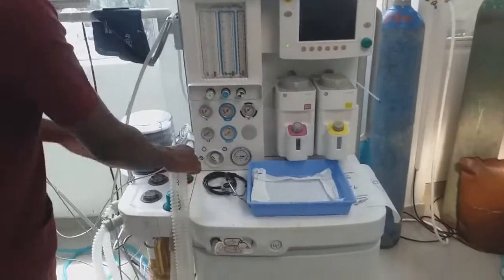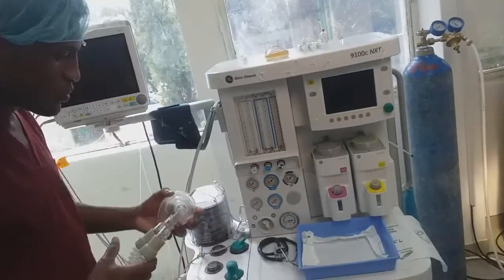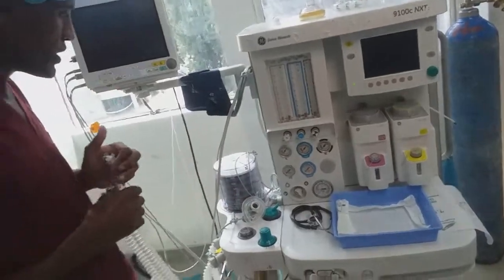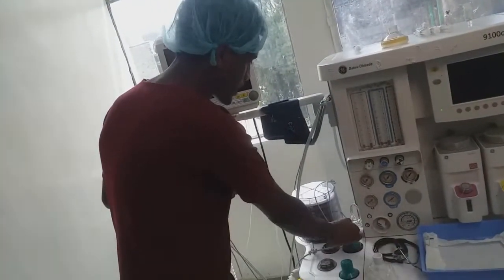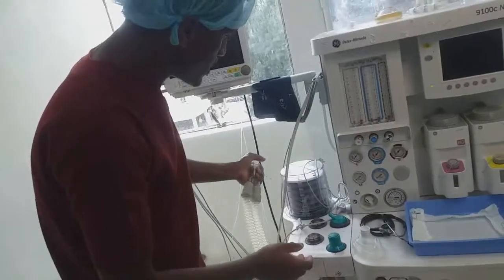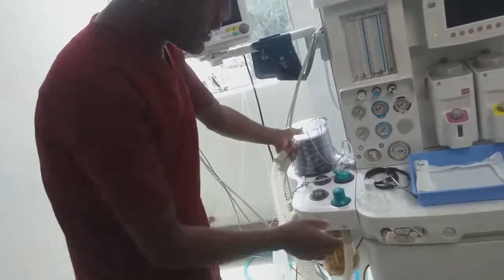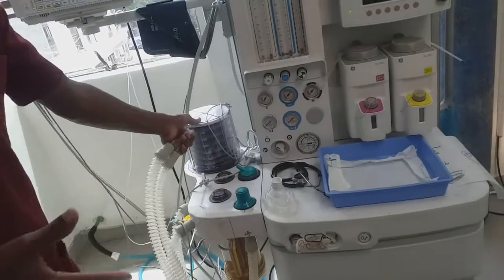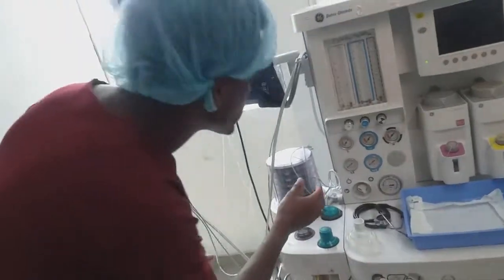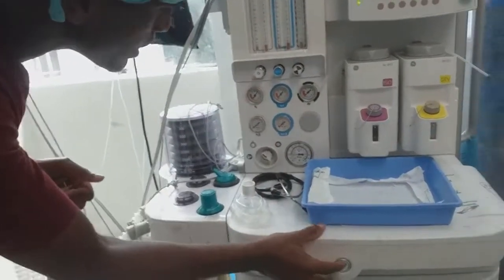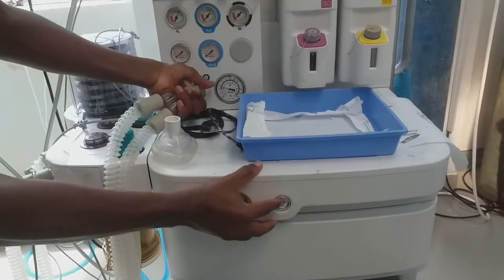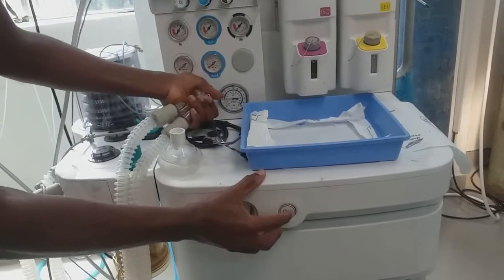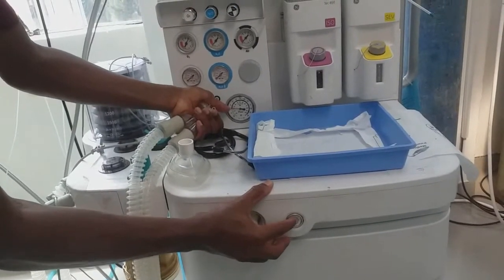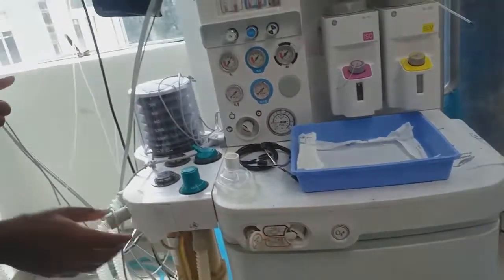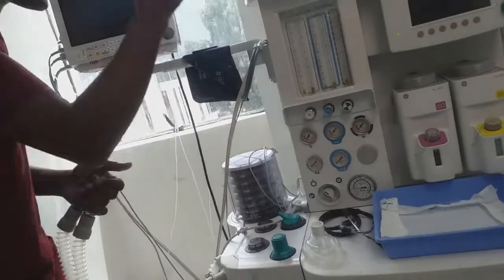To check the leak for the mechanical ventilator, I have to occlude the Y-piece, and I have to change to the mechanical ventilator mode. With the oxygen flush, I have to push this. The bellows should be filled, and the pressure should be less than 50 centimeters of water.